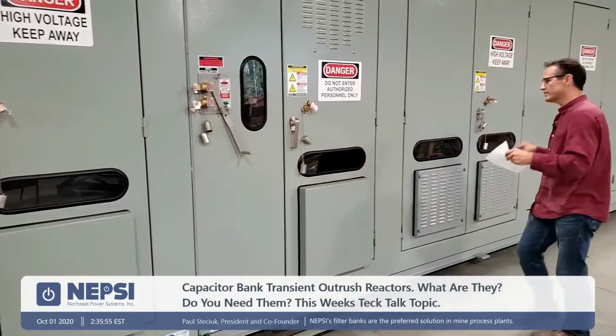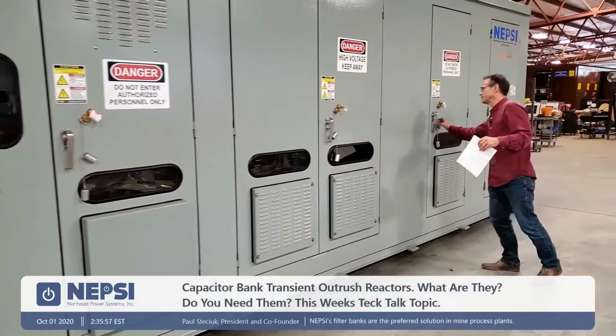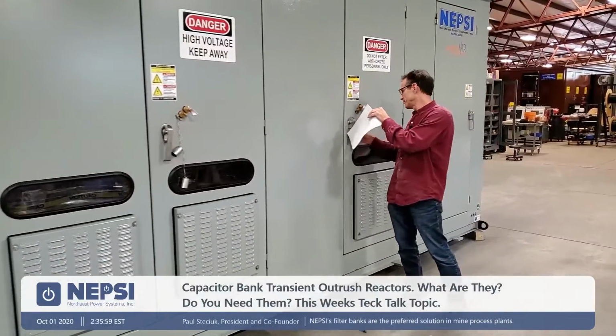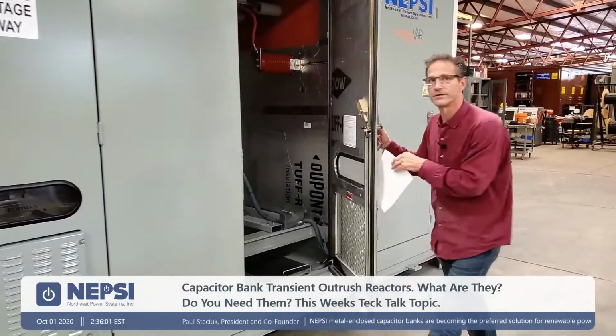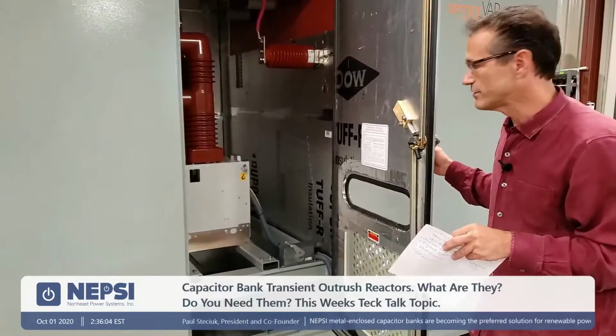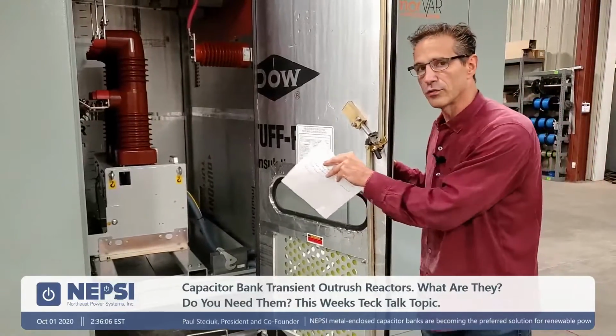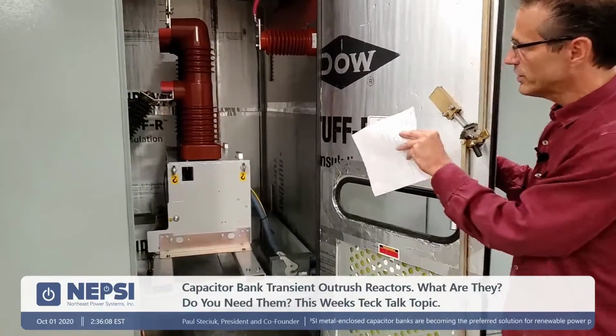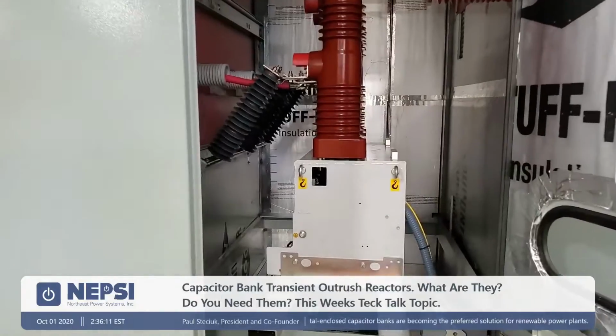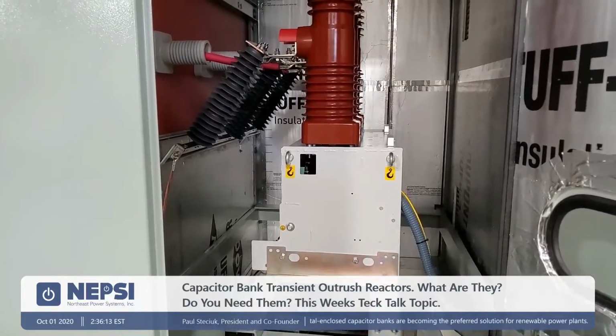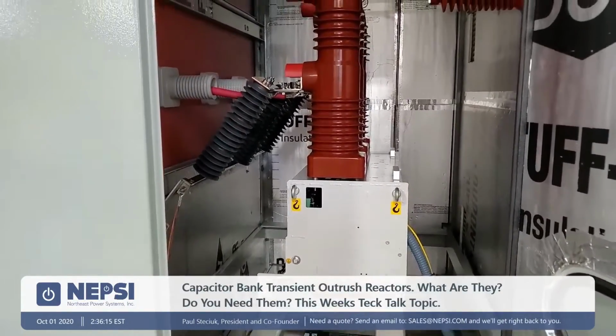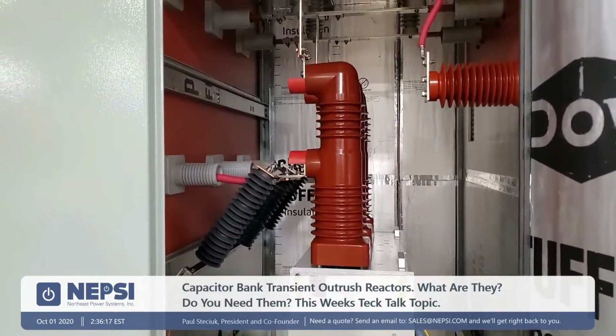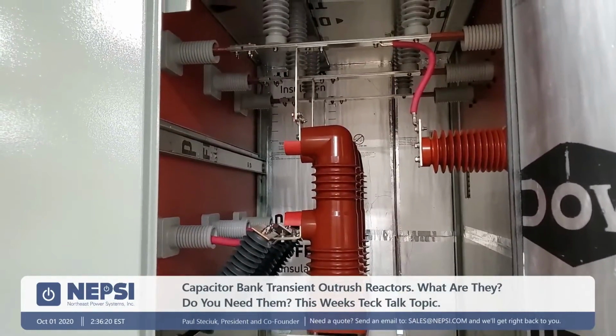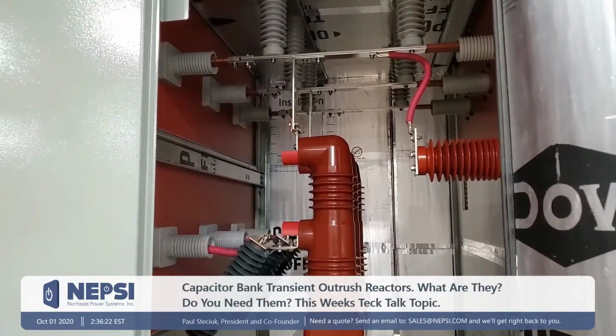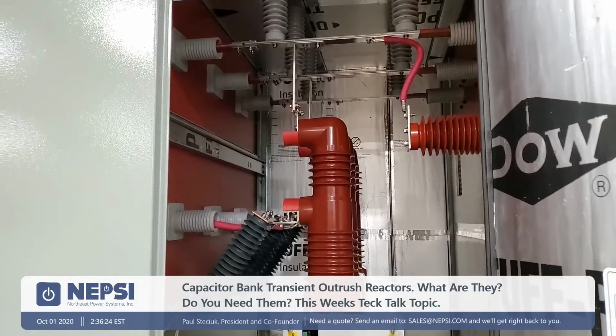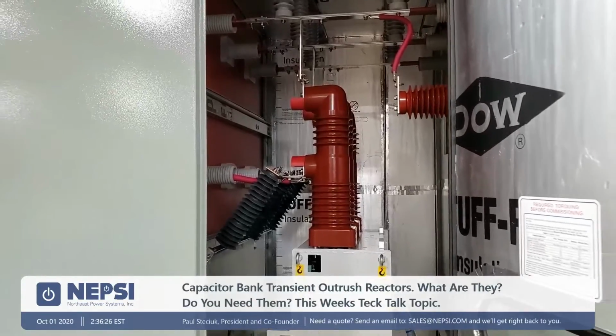So let's just talk about the switching device, because this is the new ABB VD4CS. It's a transient-free switching device, and it's installed within this system. So what you're looking at is the ABB VD4CS. It's a transient-free device. It's point-on wave switching. It has a rating of 38 kV, 185 kV BIL, 31.5 kA short circuit current, and a 1200 amp rating to it. So it can switch 1200 amps of capacitive current.